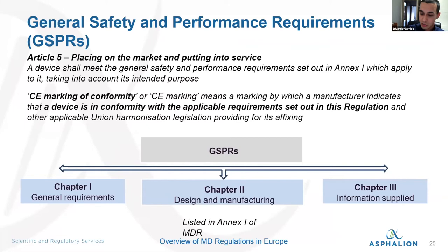What you do with all this data is demonstrate compliance with the requirements laid out in the regulation. If you go to Annex 1, you will find all the requirements applicable to your device. As a manufacturer, you have to identify which requirements are specific to your device, go through all of them, determine which apply to you and which don't, and then demonstrate compliance with them.